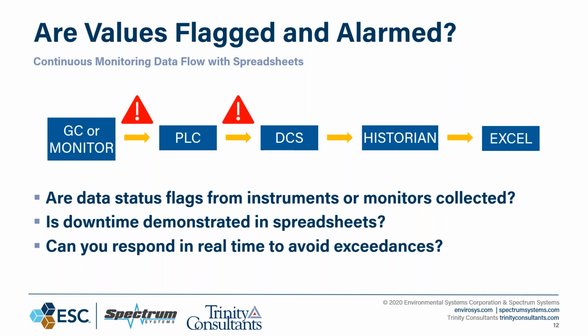Because you're collecting those status flags, that downtime should be demonstrated in any spreadsheet exports that you do, if you have the capability with your DAS. And because those values are being flagged and or alarmed, can you respond in real time to try and avoid these exceedances that we're talking about? This is very important. You want your control room operators to be able to notify somebody that there's an alarm coming in, usually generated because of those status flags. Knowing that information as quickly as it occurs allows you to respond much more quickly.